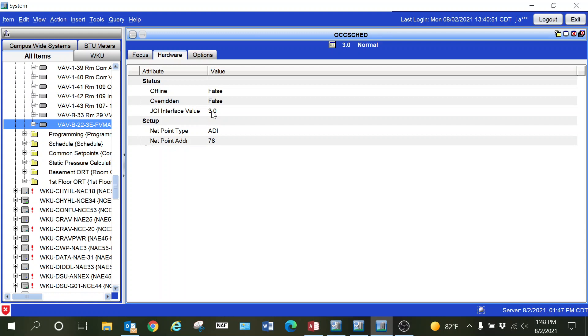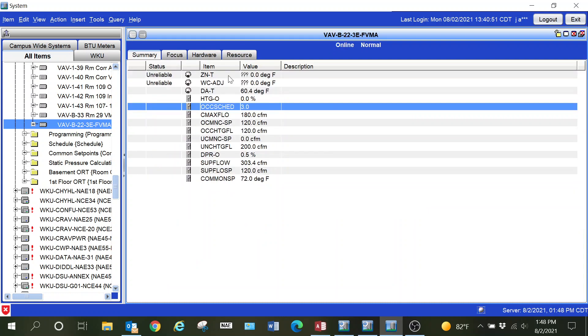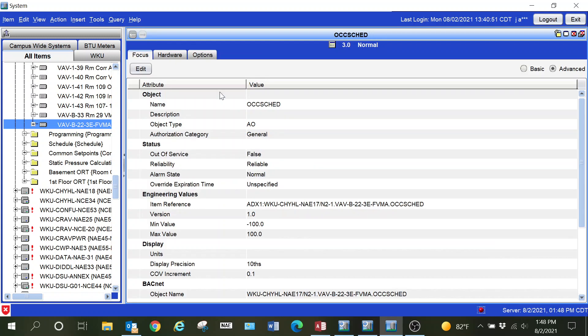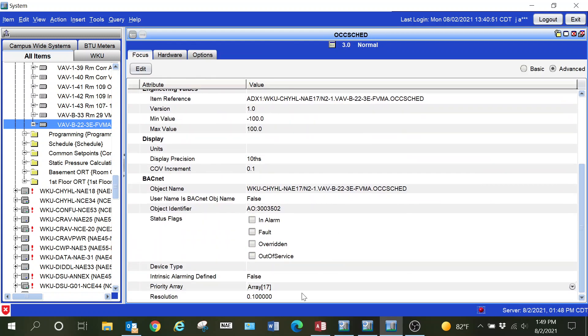You can see here it is an ADI as well as the point address. You will typically see this type of issue if you have replaced an N2 device with a newer generation device, then flip the communication and use the PRN file to pull all of the points in.